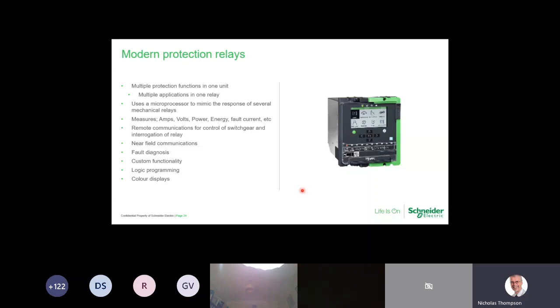You can also do logic programming in these, so the relay will go through a certain set sequence of logic with other relays when they're tied together. So you can have auto changeover schemes, you can have blocking schemes, etc. Because you're going to have amps coming in, or you might have volts coming in, you can have metering in there. Now, a word about metering: it is not what you would expect out of your separate meters.